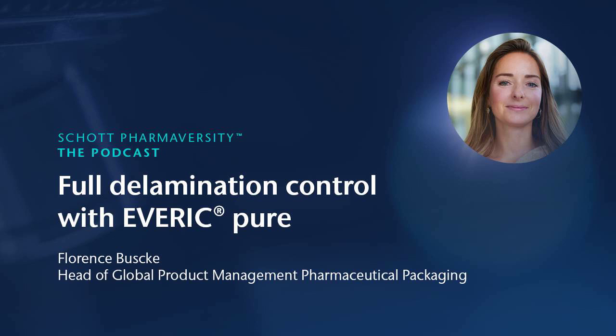But then over time we understood that we cannot look at it only from our very singular converting path. We have to include also the glass that we take. So we have worked with our tubing suppliers, and we today use the FIOLAX CHR, so that's controlled hydrolytic resistance. They do a threshold also on their tubing product to fulfill the best possible hydrolytic resistance value, so that we have even further improved and stabilized the SCHOTT Vials DC. And as it was not a real brand name, we said, following, and you know it best, to call it EVERIC Pure. So part of the EVERIC Pure is the SCHOTT Vials DC historically.